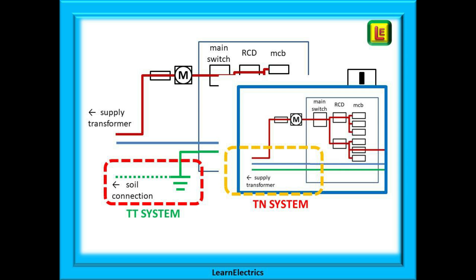We can compare here a TT system and a TN system. The TT system uses the soil as an earth path, as shown in the red box. The much more popular TN system has continuous copper conductors for phase, neutral and earth between the consumer unit and the supply transformer, as shown in the orange box.